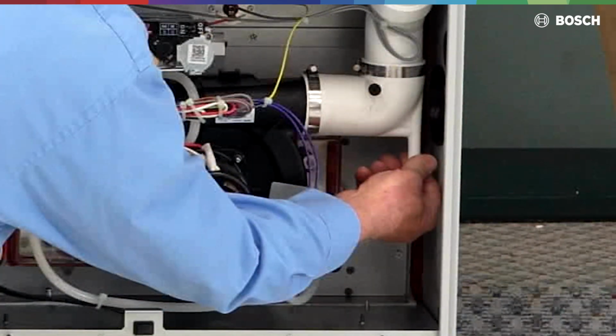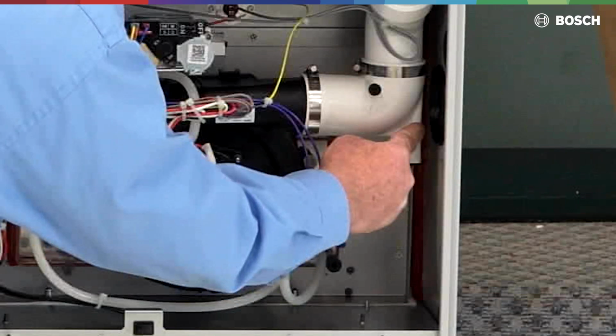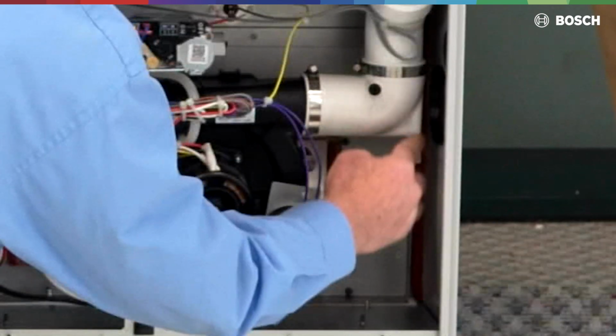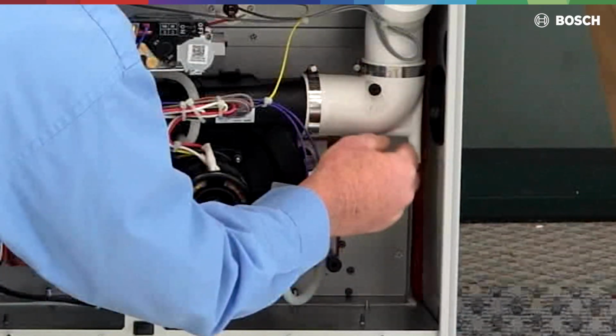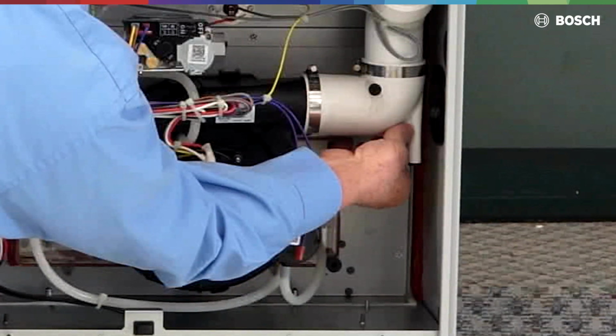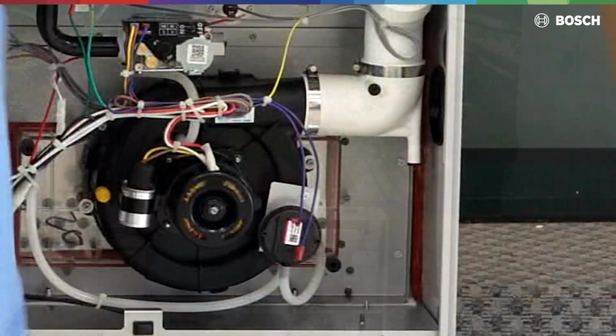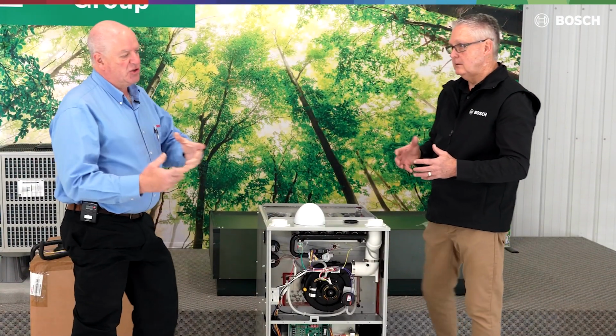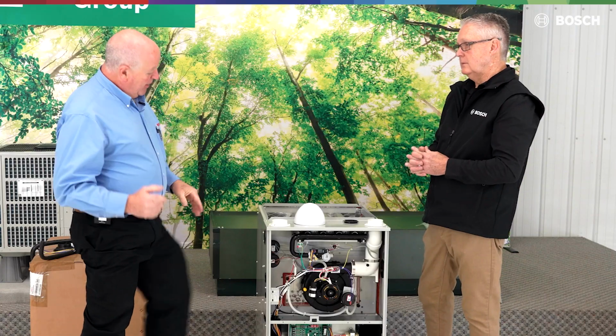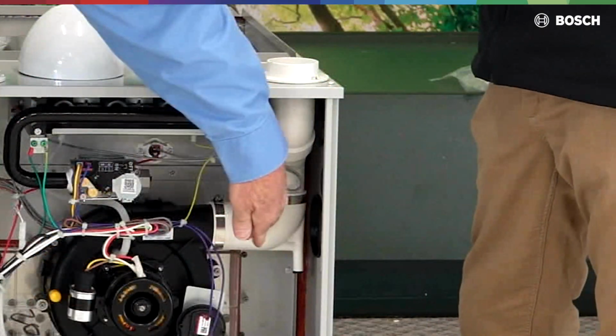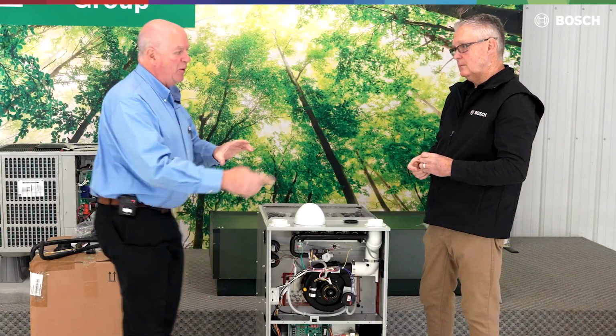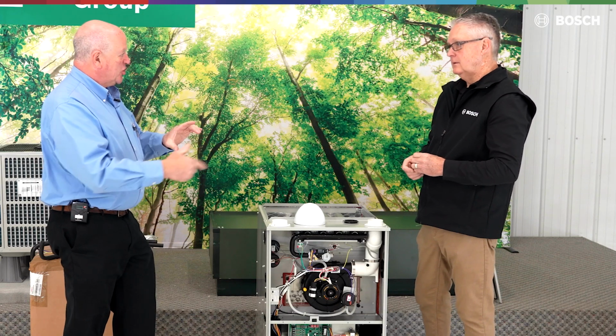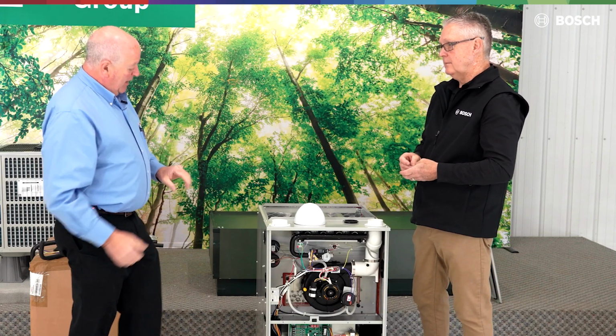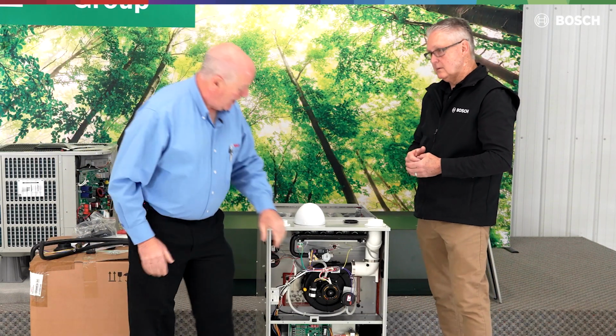There is a drain port right here. This drain port is very critical to be able to move any condensation that's coming from the blower into here. This is a small 1/8-inch tube. If this tube gets plugged up with dirt, rust, mud, whatever, that water will not drain, and what happens is the water goes back into my blower wheel, and it sounds like the Proud Mary just spitting water. Yep. If that's occurring, that typically happens about every 2 weeks. The problem is this tube coming across the bottom.